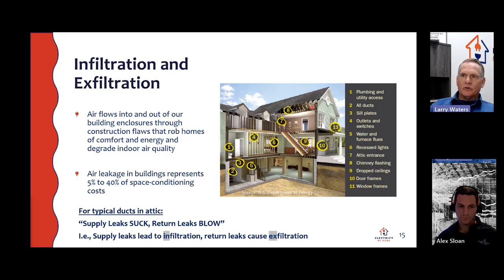So if you have your ductwork in the attic and it is leaking supply air into the attic, and you have a return underneath the furnace, that is going to create infiltration because we're pulling more air into the system than we're putting back out. We're leaking some air above the pressure boundary, which means we're pulling a negative pressure on the inside boundary, which means that's going to cause infiltration. So supply leaks lead to infiltration.